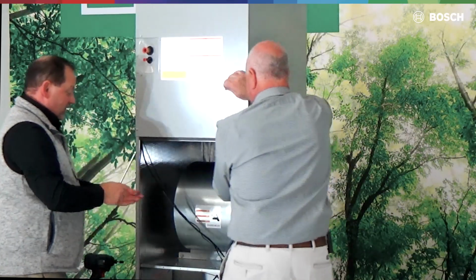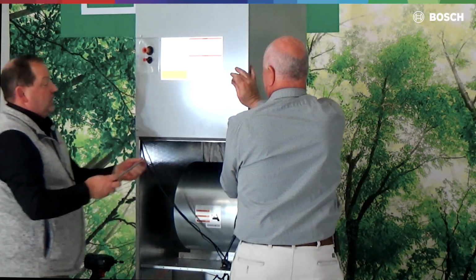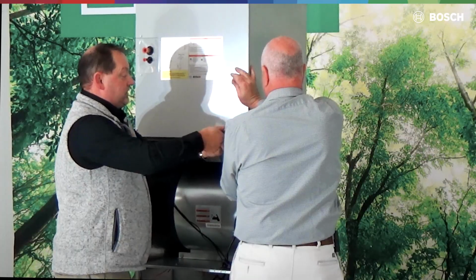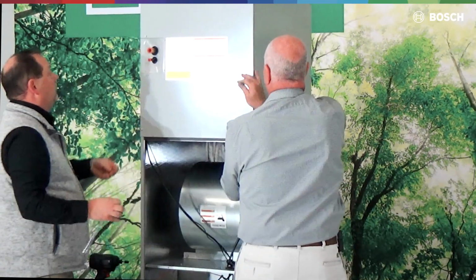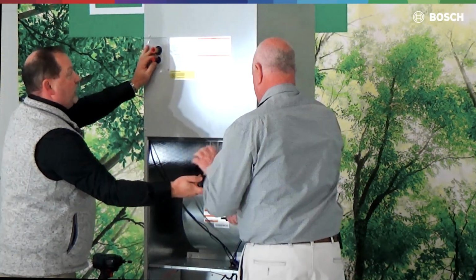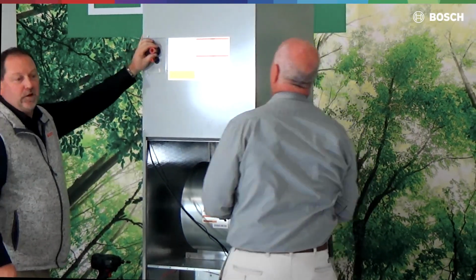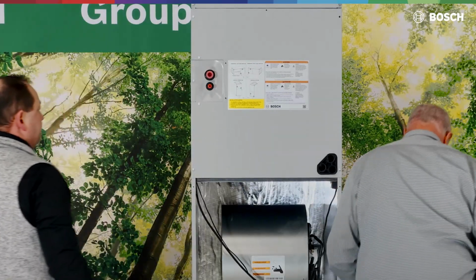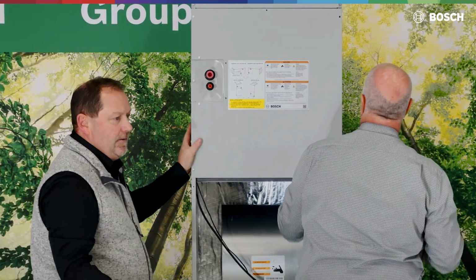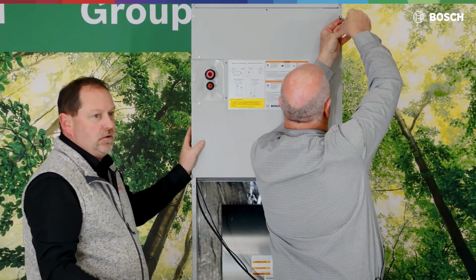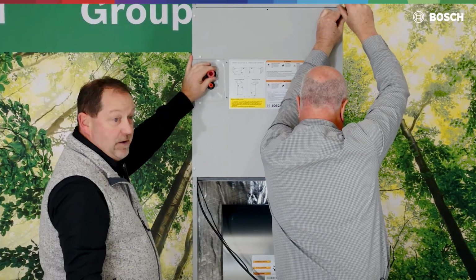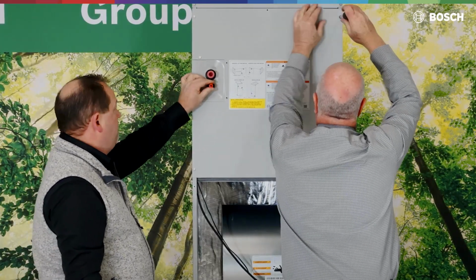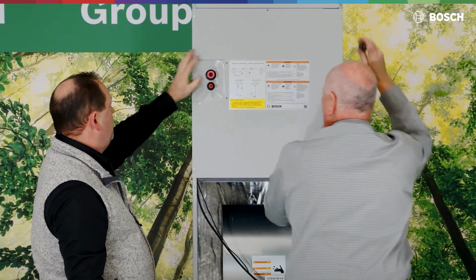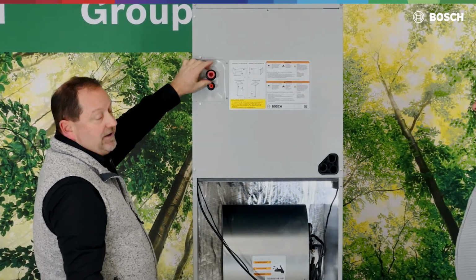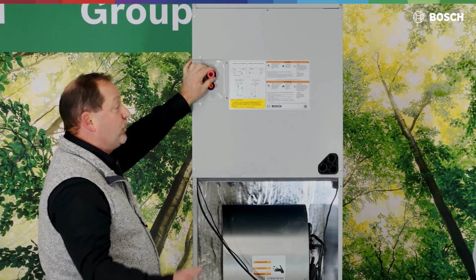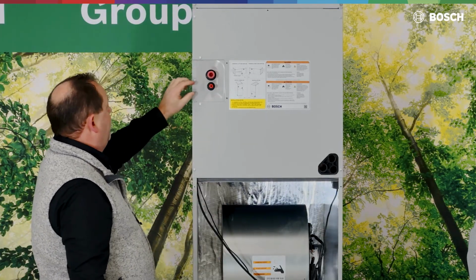Righty-tighty, loosey-lefty, Chris. Another thing that has been a great addition to our new product here is that we are now approving, if you want to catch that side, Dave, mechanical fittings, okay? A mechanical fitting is going to be a press type fitting that would perhaps eliminate the need for a braze joint. And by doing so, we may need to connect that fitting on here before the door gets put on, okay? Pro Press, I believe, is the name of it. Pro Press, Mueller has them, Zoom Lock.